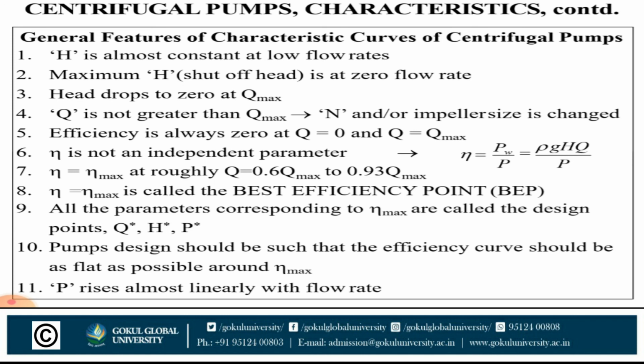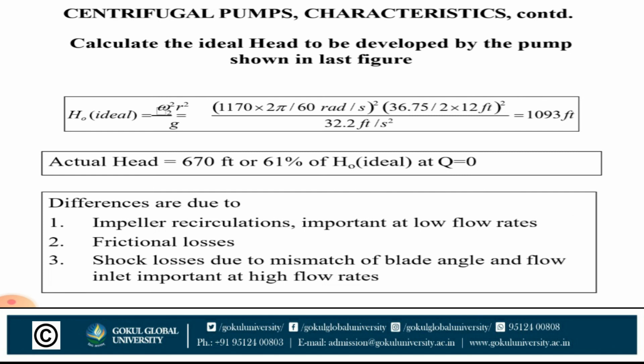Power, discharge and head. The pump design should be such that the efficiency curve is as flat as possible around maximum efficiency. P rises almost linearly with flow rate. Some differences are due to impeller recirculation, important at low flow rate, and frictional losses and shock losses due to the mismatch of blade angle and flow inlet, important at high flow rate.